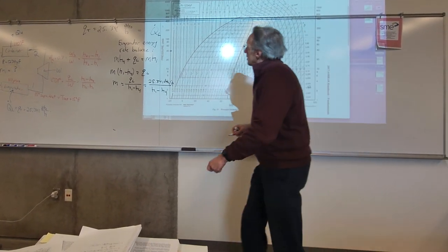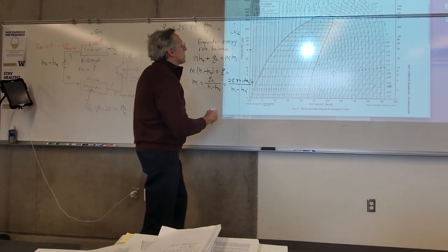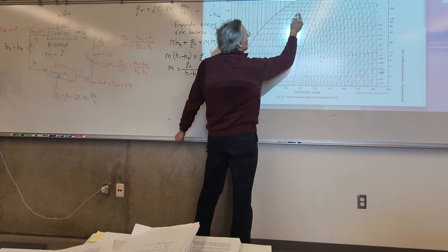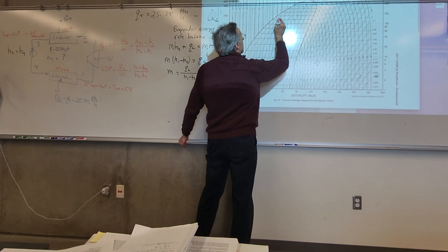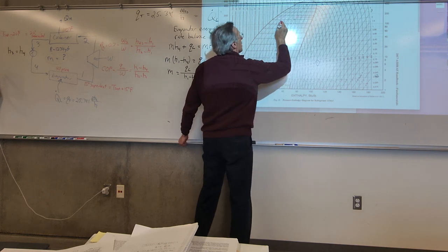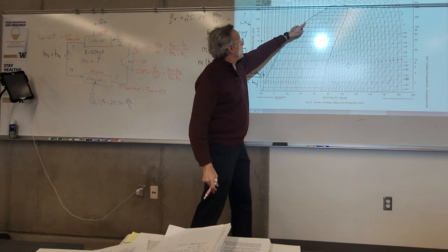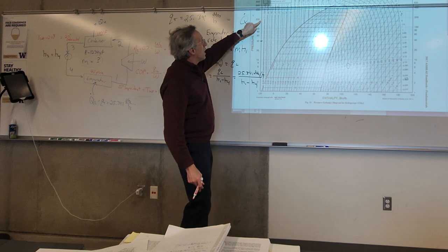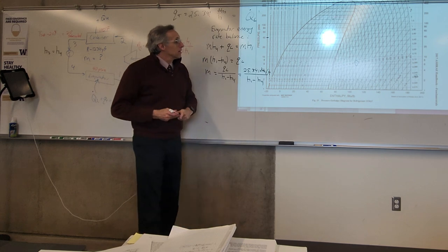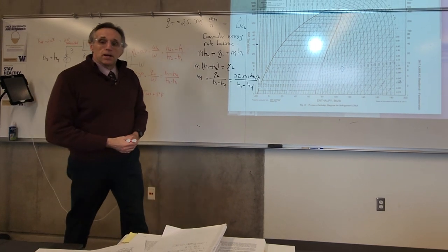Now, if we're at 110 degrees in the condenser, that means we're going to be right in between. So our condenser is going to be operating right there. And then to get the pressure, we just read over to the vertical, and it's about, what, 180 or something like that? But I'm just eyeballing it here. I'm going to go to another diagram where I filled it in.